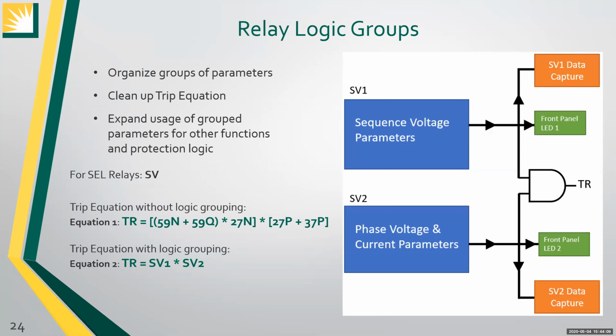And lastly, the final component to our detection logic design, relay logic groups. Relay logic groups are simply groups of parameters and their logical circuits grouped into one singular representative equation. For Schweitzer Engineering Laboratory relays, relay logic groups are represented by SV. They are used for mostly 3 reasons: they help organize special groups of parameters, they help clean up trip equations, and they help expand the usage of group parameters for other relay functions.